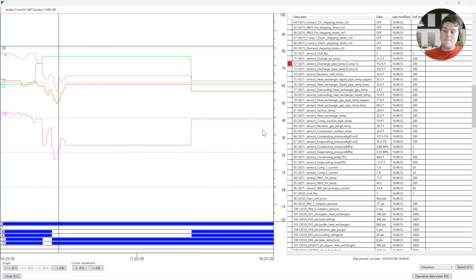Not only does it defrost, does the gas go to the right place, is it the right temperature, that's four-way valve checking operation, that's quick and easy. Also, the duration of defrost. Now, we know that one is much longer than the other, an hour long, which is insane, unless we're talking sub-zero temperatures for my boys out in Canada, right? It's not, right? So when we look at these two, that's a problem.